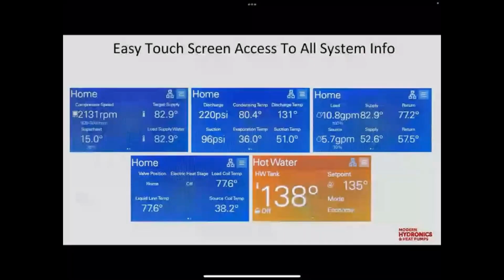So it really eliminates the need for any sort of diagnostic tools. Really, the only reason to ever hook any diagnostic tools to this is to verify that you have a bad sensor, whether it be a thermistor or a pressure transducer. We also show information like the valve position down here. Are we in the home mode for space conditioning, or are we doing domestic hot water? And if we have electric heat stages, the 9 kW is broken up into three 3 kW stages, or are we running the backup boiler? And then what the actual temperatures are of our load and source coils.